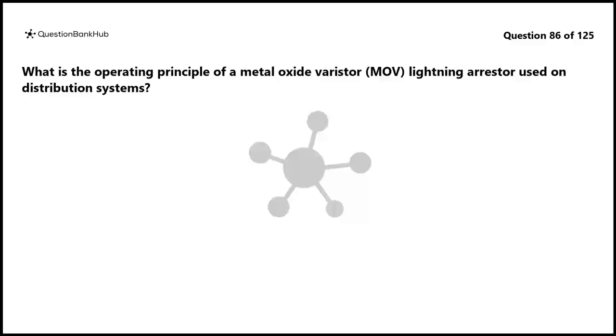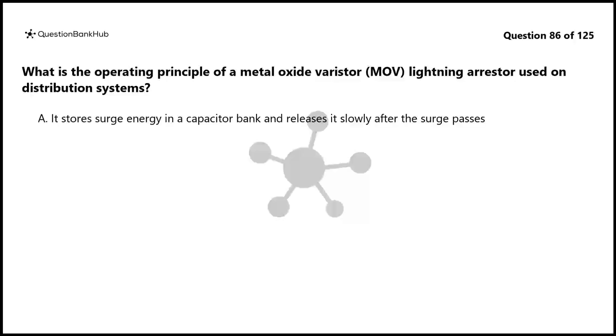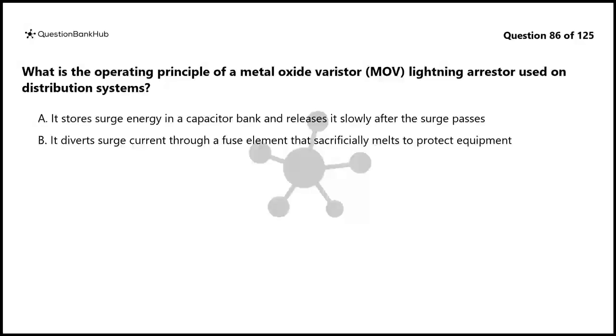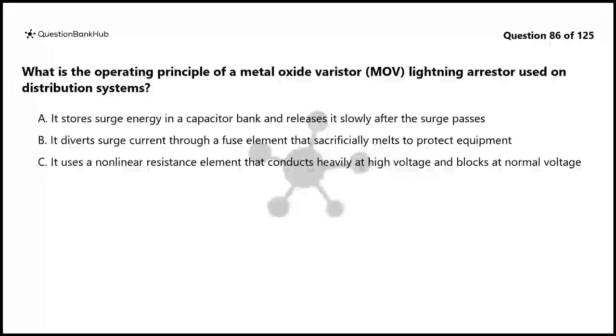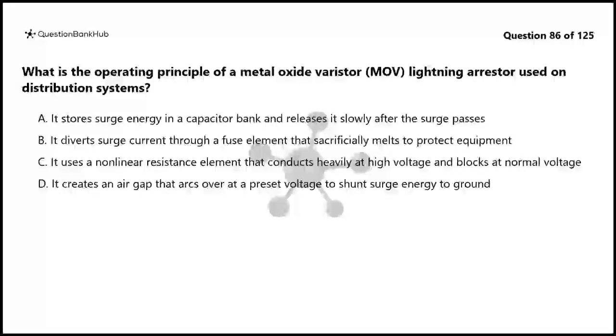Question 86. What is the operating principle of a metal oxide varistor, MOV, lightning arrestor used on distribution systems? A. It stores surge energy in a capacitor bank and releases it slowly after the surge passes. B. It diverts surge current through a fuse element that sacrificially melts to protect equipment. C. It uses a nonlinear resistance element that conducts heavily at high voltage and blocks at normal voltage. D. It creates an air gap that arcs over at a preset voltage to shunt surge energy to ground.